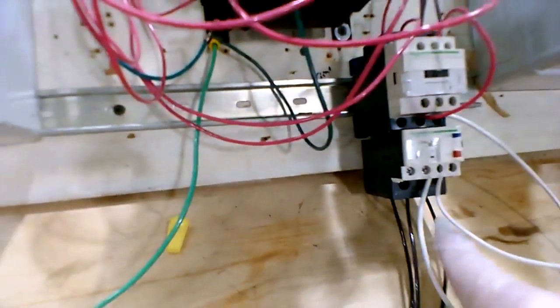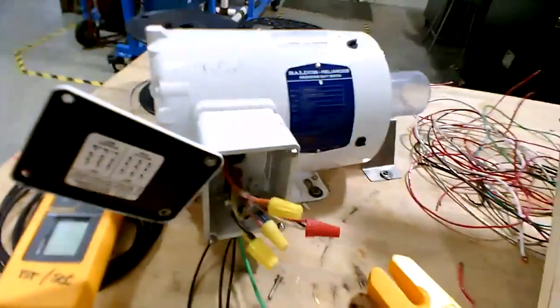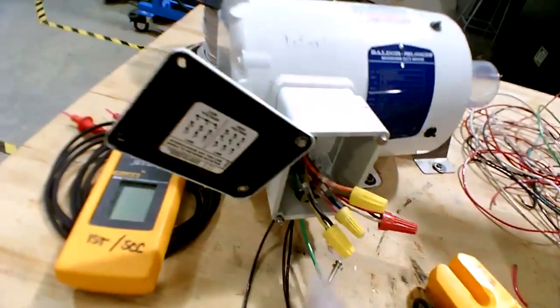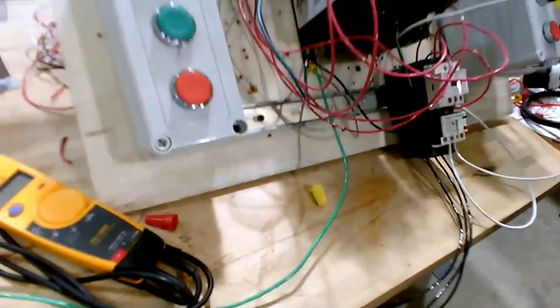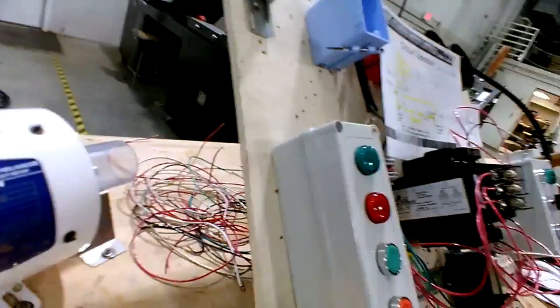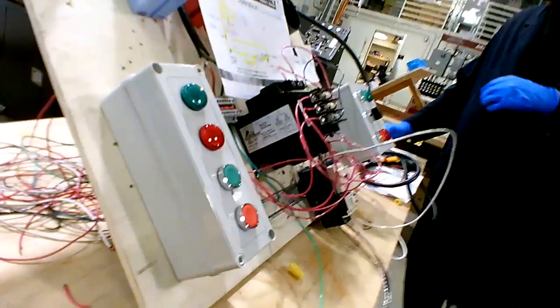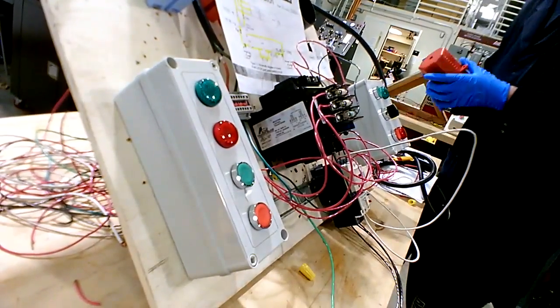It can be done at that point, above or below, or it can actually be done at the motor. You can come in here and reverse them, but it's best to do it wherever it's most convenient and quick. It's actually faster to do it here than to undo the wire nut. So we're going to lock it out. Put the lock back on it.